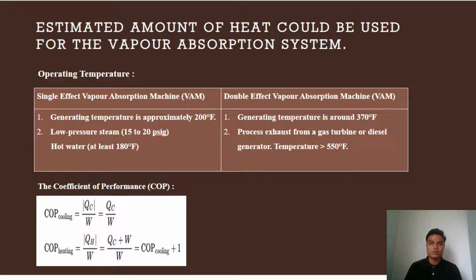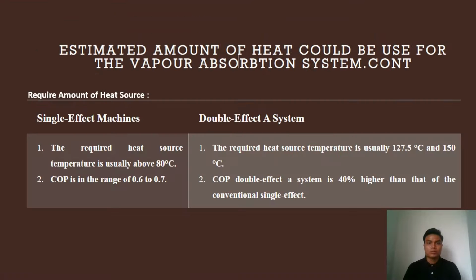Next, efficiencies of vapor absorption machine. Absorption chiller efficiency is measured by the coefficient of performance, COP, which is the cooling effect in BTU divided by the net heat input in BTU. This figure shows the formula for COP cooling and COP heating. Next, for the required amount of heat source. The required heat source temperature is usually above 80 Celsius for a single effect machine, and the COP is in the range of 0.6 to 0.7.